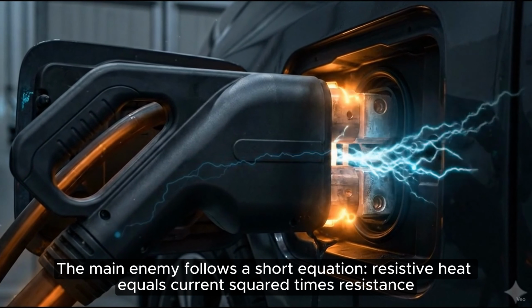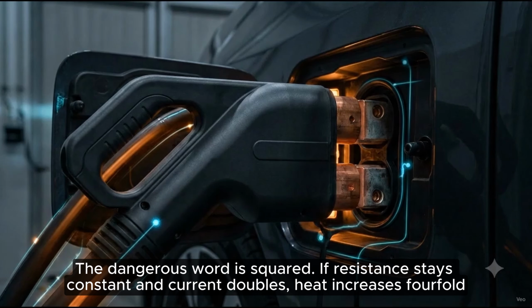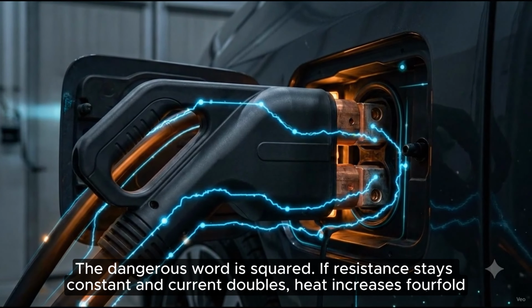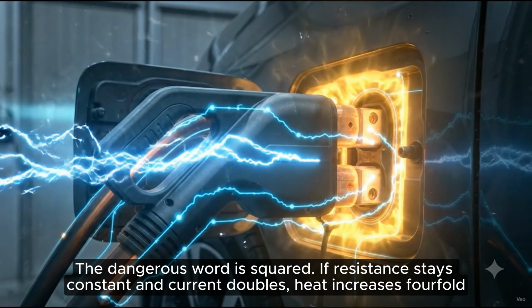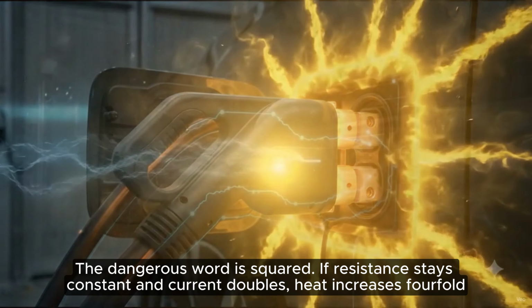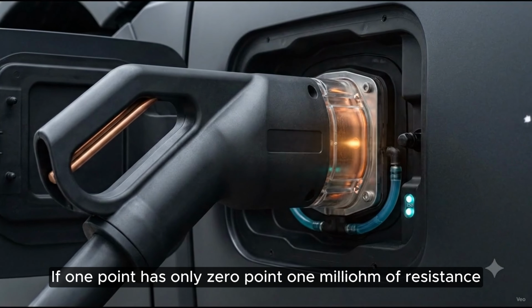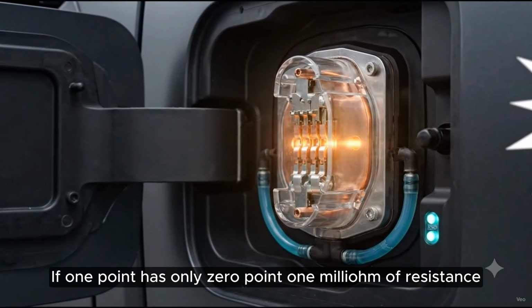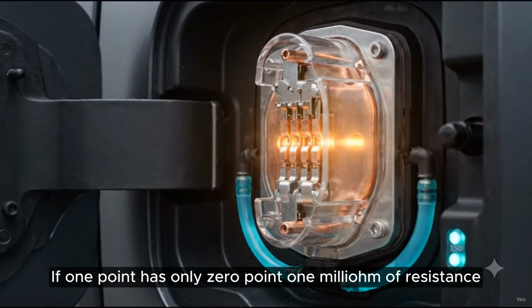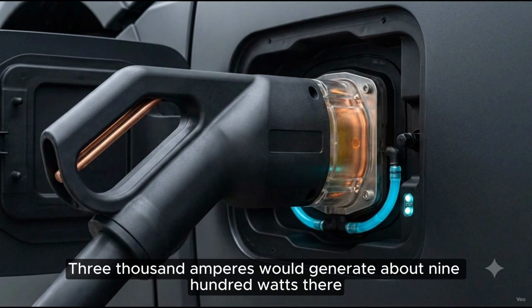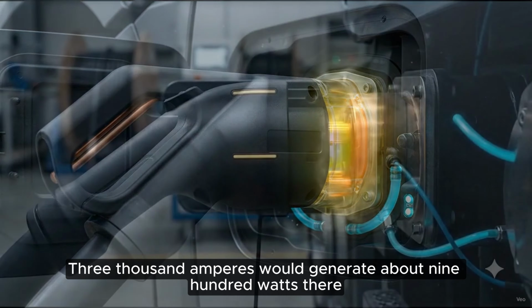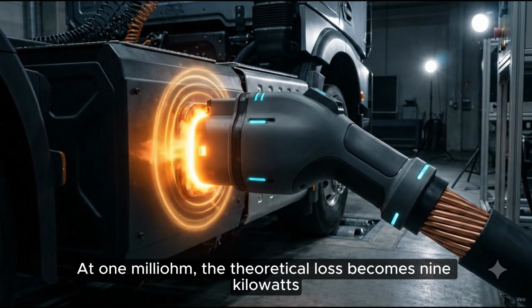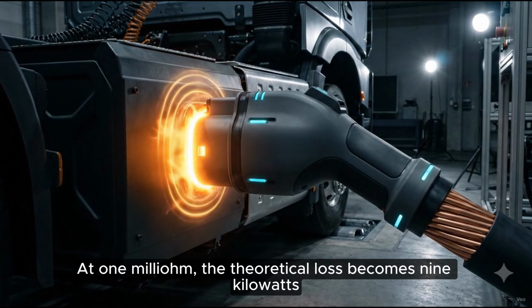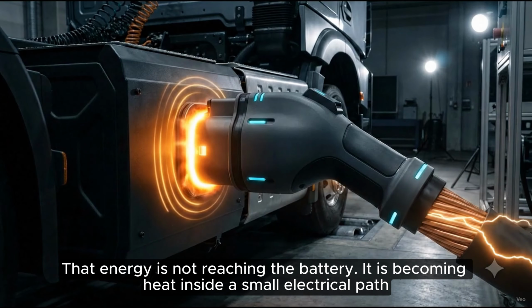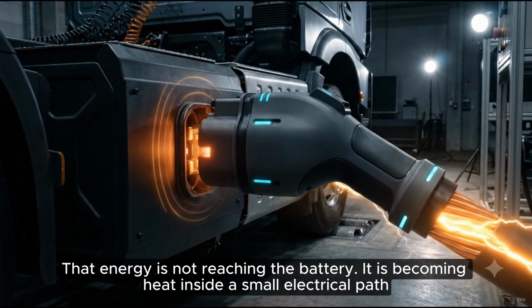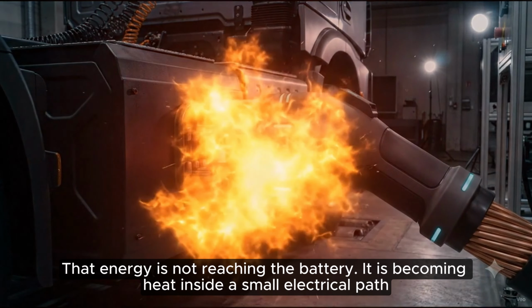Resistive heat equals current squared times resistance. The dangerous word is squared. If resistance stays constant and current doubles, heat increases fourfold. If one point has only 0.1 milliohm of resistance, 3000 amperes would generate about 900 watts there. At 1 milliohm, the theoretical loss becomes 9 kilowatts. That energy is not reaching the battery. It is becoming heat inside a small electrical path.